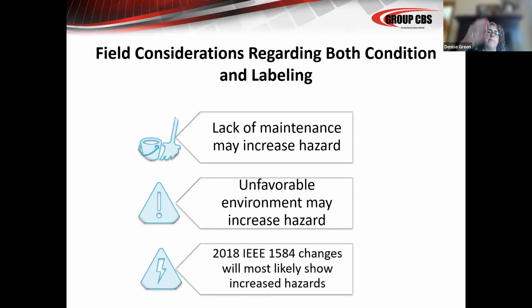On this unfavorable environment, keep in mind when you're doing things in your plants, it sounds really easy to tell the janitor, hey, go sweep up that substation. There's a lot of dust on the floor. I don't want the dust in that substation. Go take a broom and go take care of that. That act of creating an unfavorable environment can cause an arc flash explosion. So being cognizant of what an unfavorable environment is really important, in and above the actual day-to-day presence of chemicals, contaminants, air pollution, all of that stuff. So keep that in mind for what's going on in your plant.